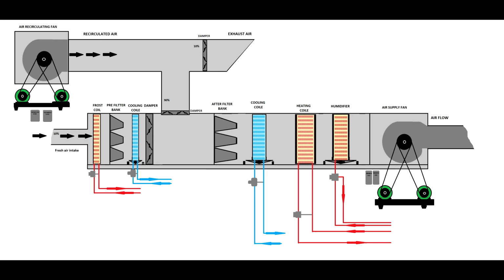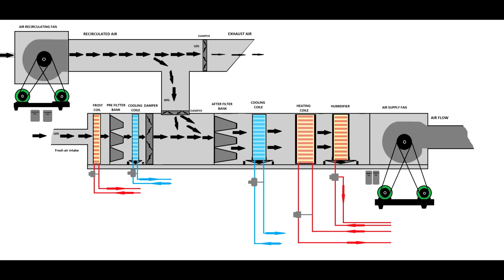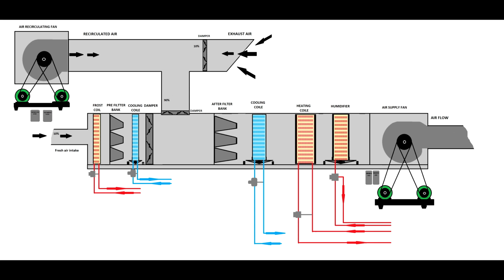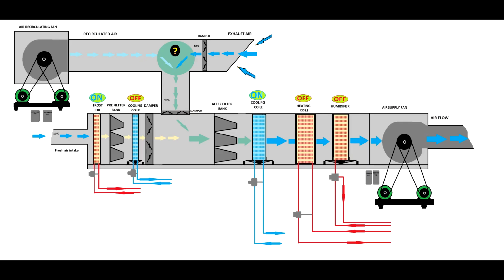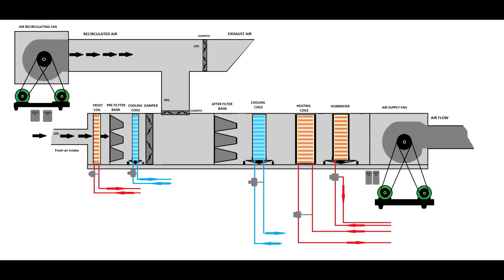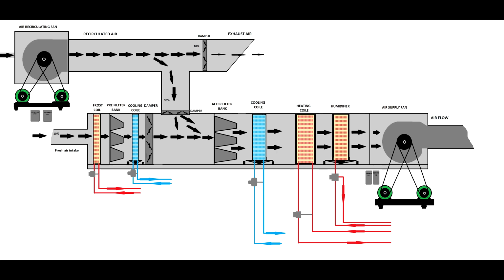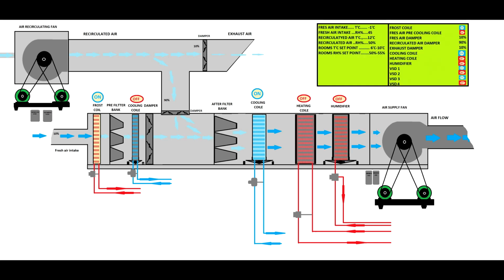When the air comes back through the exhaust, that's very bad, because that air bypasses the frost heat exchanger, the primary filter, and the primary cooling coil, so you will not have any control. I call it dirty air, which gives us a lot of headache. So that's not good. What you see in this picture should not happen. Unfortunately, sometimes it does happen. So you only have to look into the system to see this condition, so the air circulates that way.